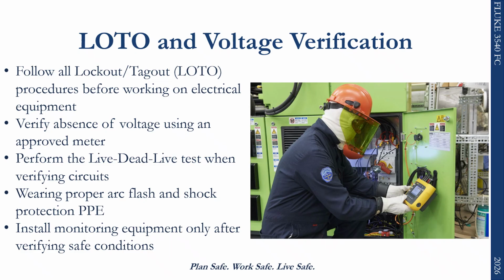Before installing monitoring equipment on any electrical system, proper lockout-tagout procedures must always be followed. Workers must verify the absence of voltage using an approved meter and perform a live-dead-live test when verifying circuits. Proper arc flash and shock protection PPE must be worn when working around electrical equipment. Monitoring devices should only be installed after safe conditions have been verified.